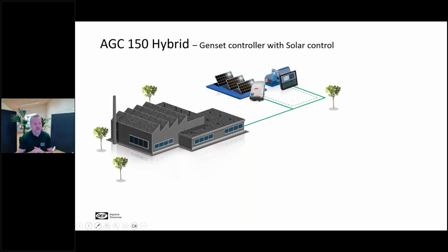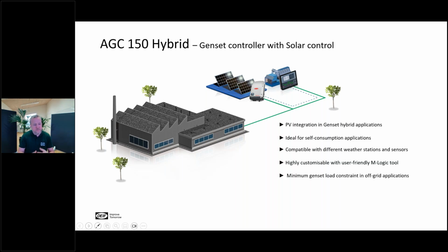The AGC 150 Hybrid is what we call a genset controller, but we have added the PV controls to it. So it is able to sit on a genset, be the genset controlling unit, and then communicate to the Fronius inverters and control them according to what Christoph was showing in the beginning. So it is, of course, a controller that's ideal for PV integration with gensets, local consumption, but we also have the possibility to connect our own plane of array sensors and back of module sensors, because then we can calculate what we can take out of the PV system, of the Fronius system, when we are in control of it.